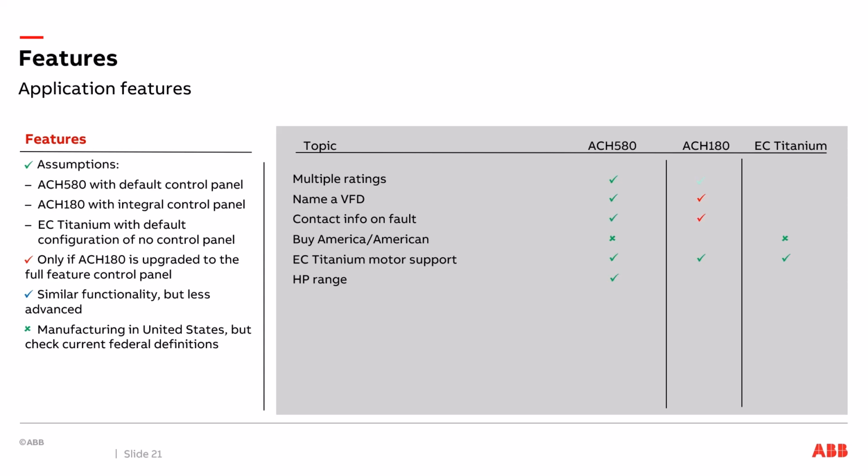Being able to name the VFD. So maybe I'm supply fan 2, or pump 3, or chilled water pump 2A, or something like that. On that advanced control panel, if you've got that advanced panel, you can actually name the application in the top middle of that control panel. It's customizable.